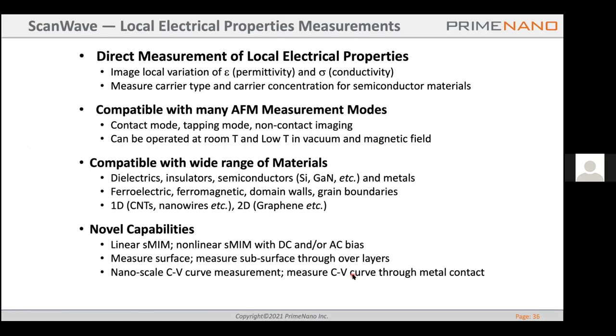Okay, let me give a summary of this talk. Scanwave sMIM is a local electrical property measurement. It can directly measure the local electrical permittivity and conductivity. For semiconductor samples, it can measure the carrier type and the carrier concentration. It's compatible with many AFM measurement modes, for example contact mode, tapping mode, and non-contact mode imaging, for example nap mode and peak force tapping. It can be operated at room temperature and also at low temperature, in vacuum, and with magnetic fields.